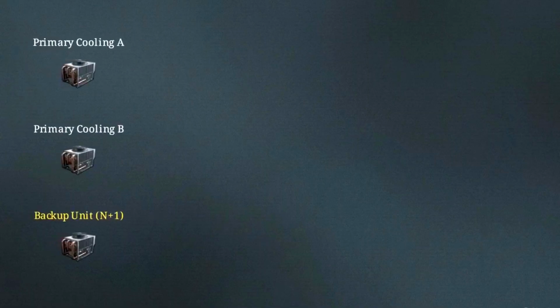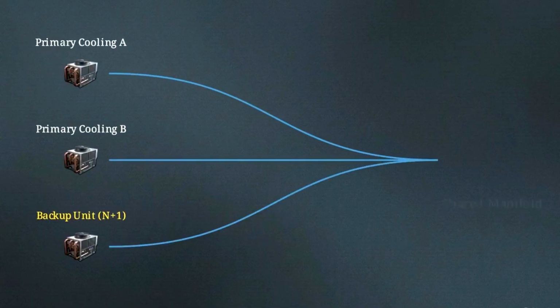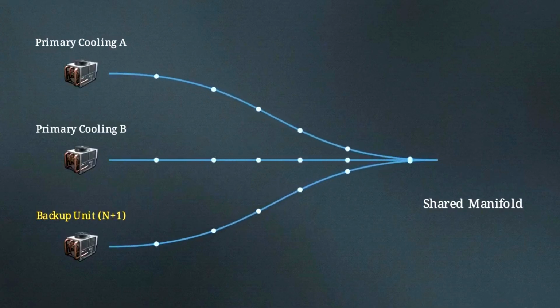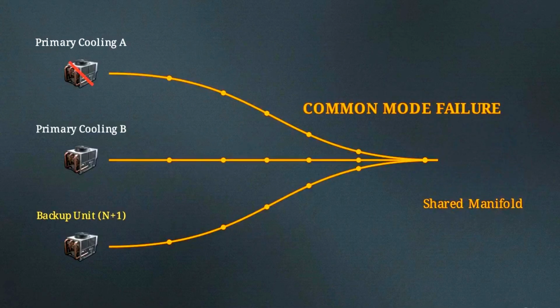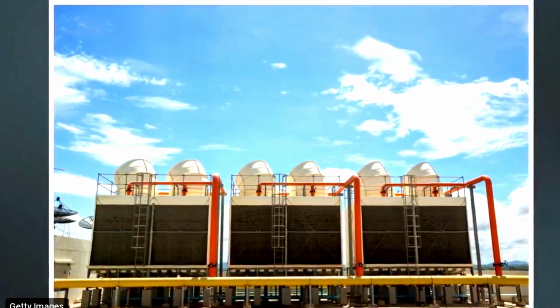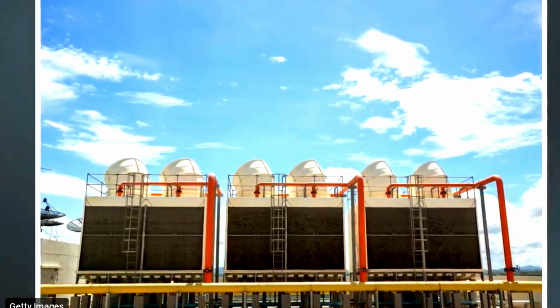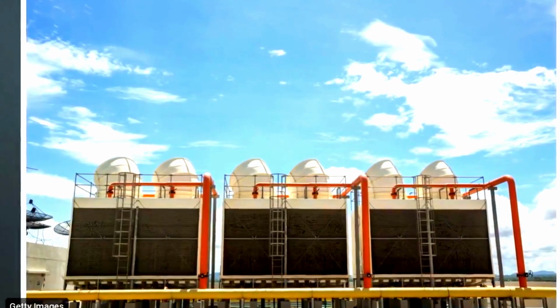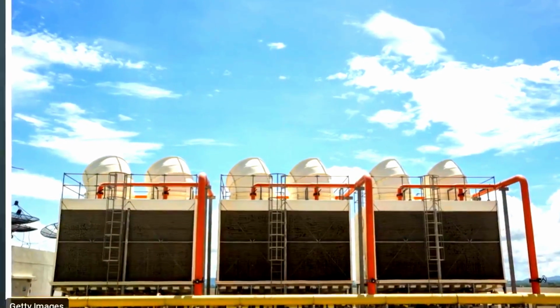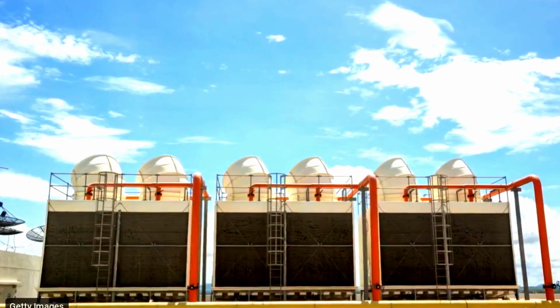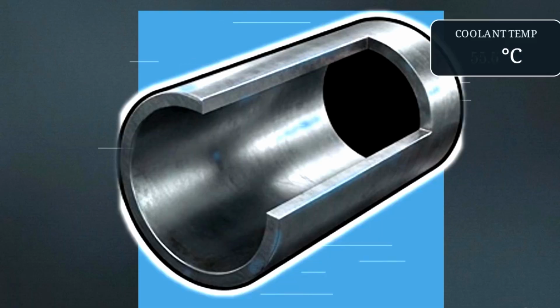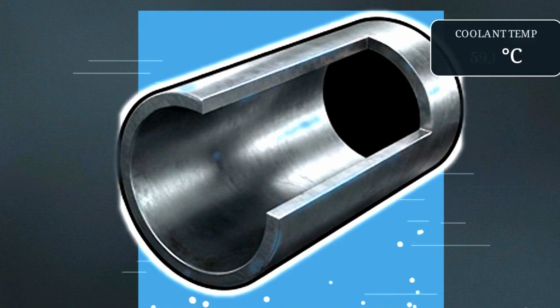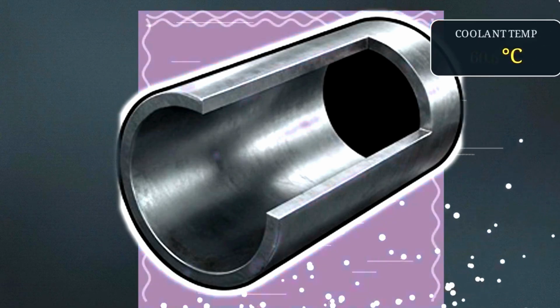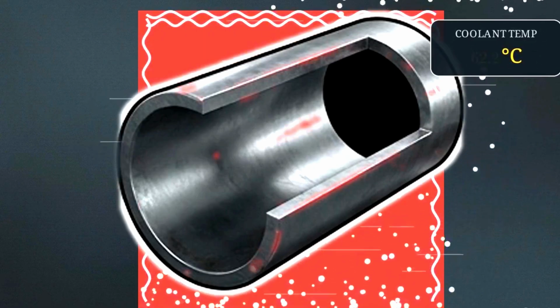The cooling design relied on a redundancy fallacy. While there were multiple backup units, they were all routed through a single shared coolant manifold pipe. When ambient air reached 41 degrees, the mechanical stall began. The rooftop heat exchangers became completely unable to reject heat into the superheated outside atmosphere. Inside the servers, the internal cooling loop spiked to 62 degrees. This exceeded the 60-degree boiling point of the dielectric fluid inside the pipes.